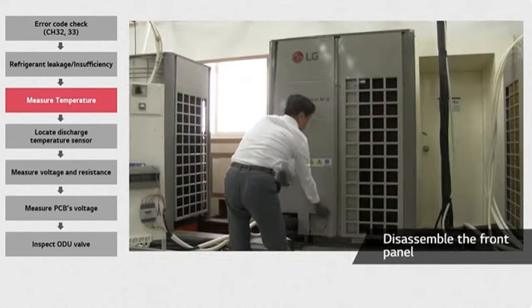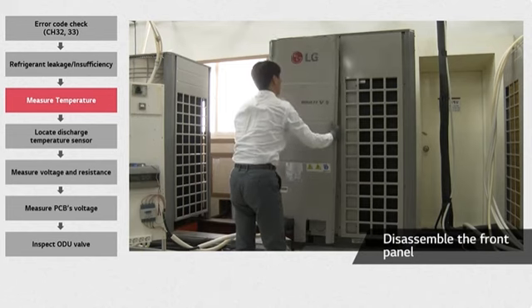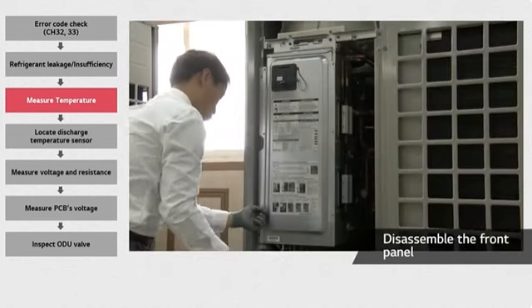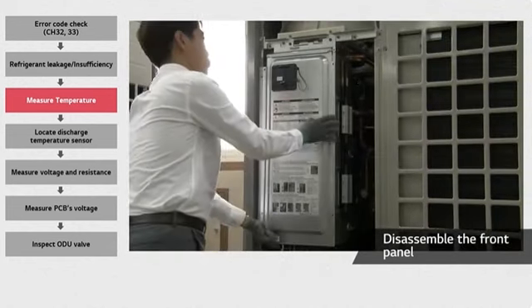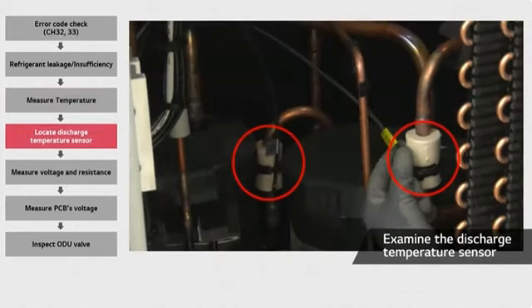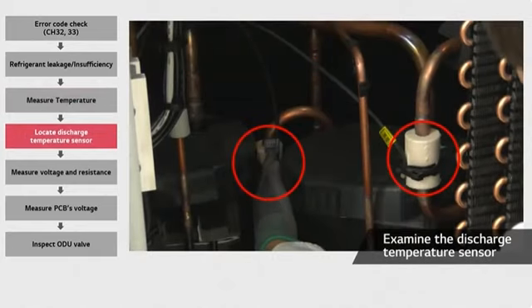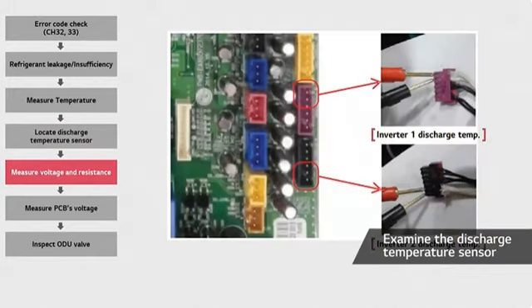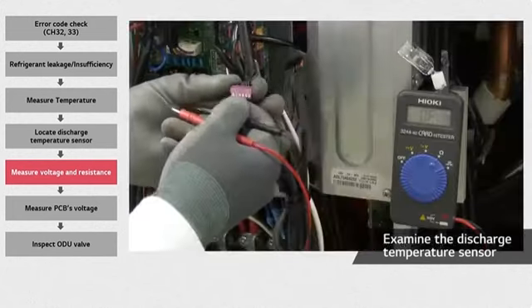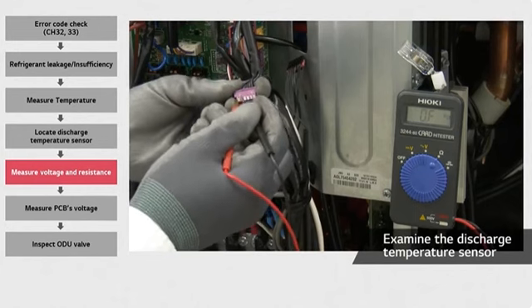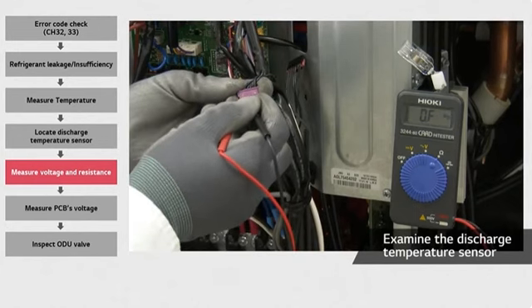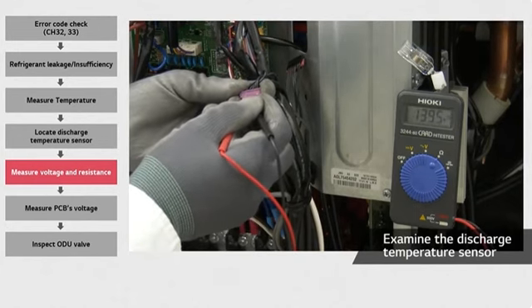First, remove the front panel on the outdoor unit, and then disassemble the control box of the outdoor unit. Check that the discharge temperature sensor is in the proper location. Measure the resistance across the two lines of purple and black connectors connected to the external PCB. This error will occur if the value is greater than 5 megaohm or smaller than 2 kiloohm.